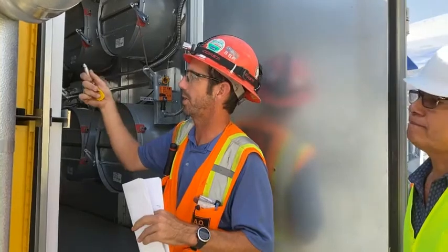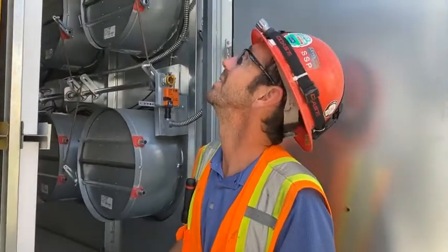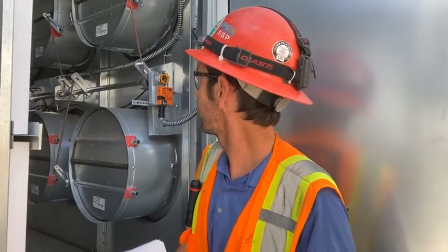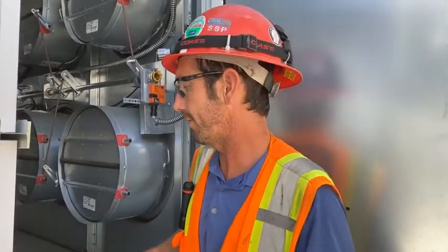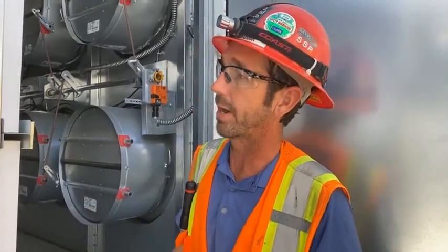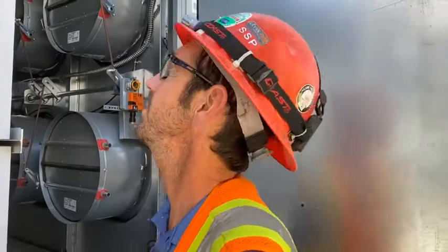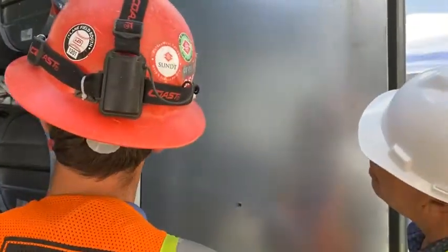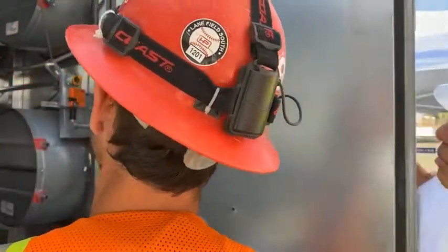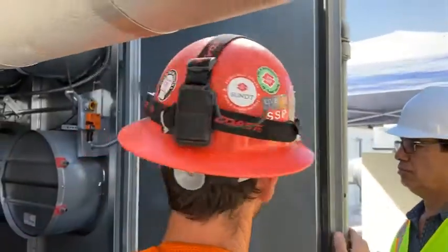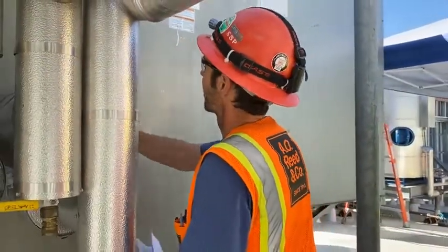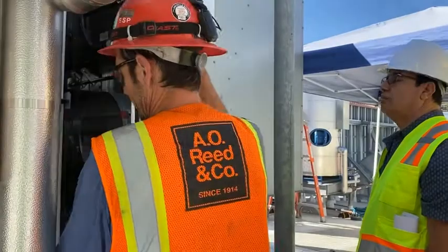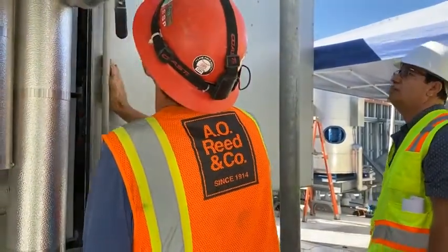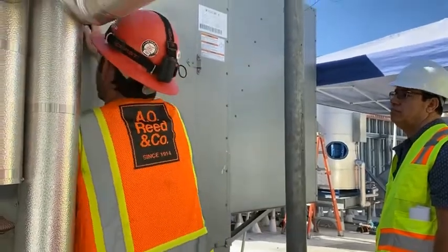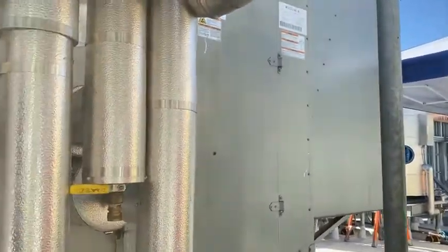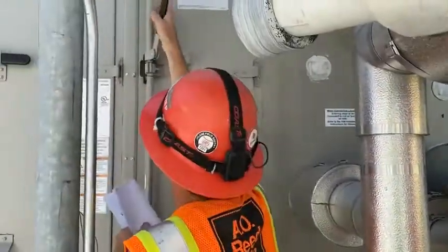Controls is monitoring the pressure drop across the filters, but it's the whole rack. When you do your inspections in here, if there is a lot of debris, you'll want to clear the debris out of the compartments. Any questions on the filters, outside air openings? Don't have to grease anything here. No greasing here. It appears the unit's off right now too, so. Next compartment down.